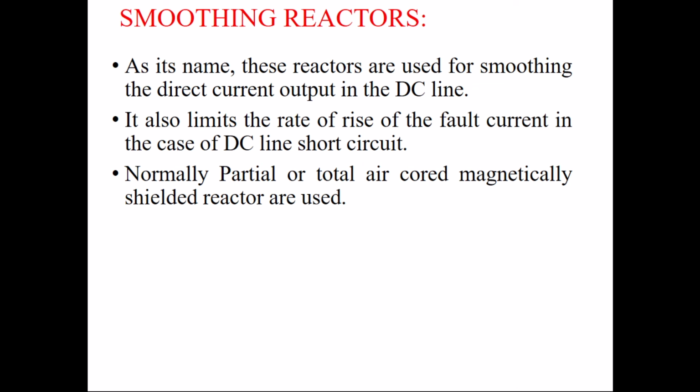So at that time we must maintain this current to a reasonable value. At that time this reactor helps to reduce the rate of rise of this fault current in transient condition. But in steady state condition, we know this reactor is basically nothing but an inductor. So in steady state condition this reactor works as a short circuit.